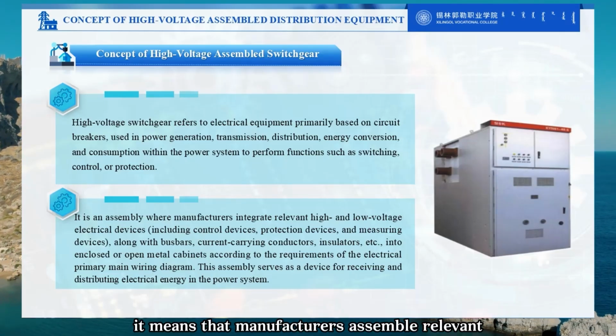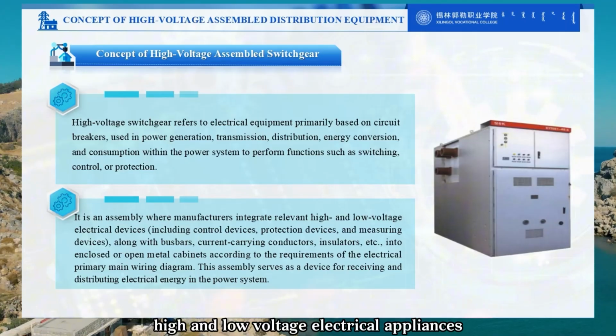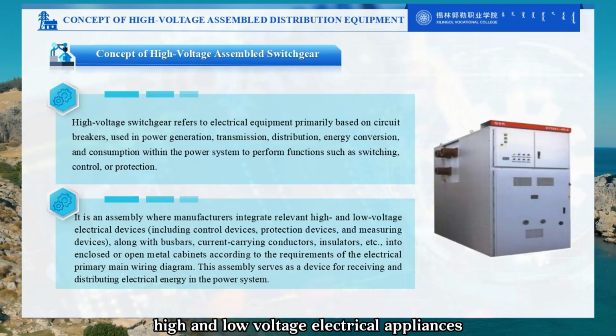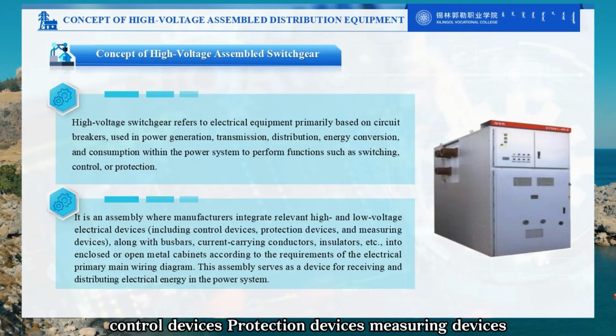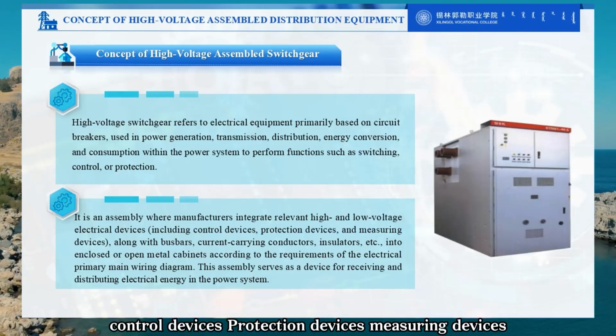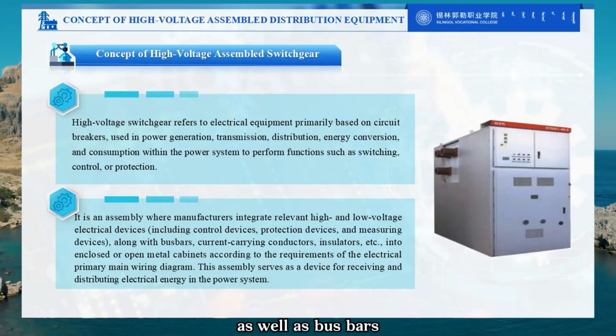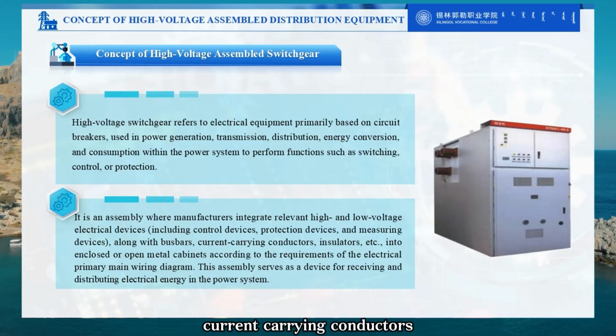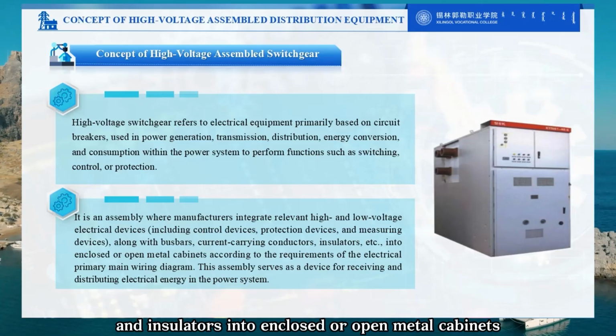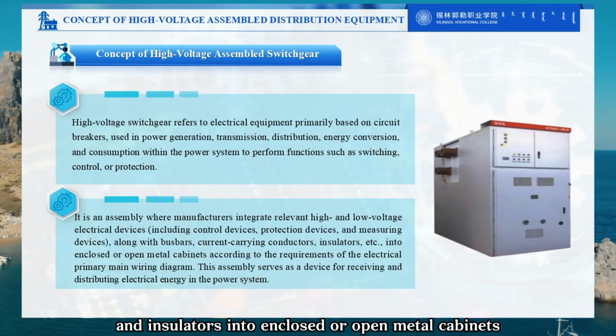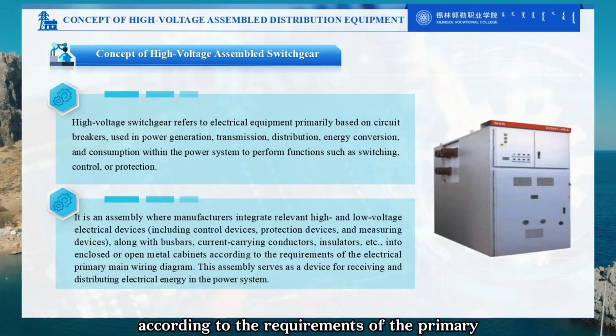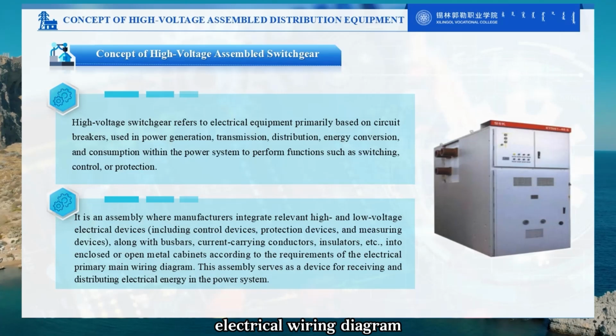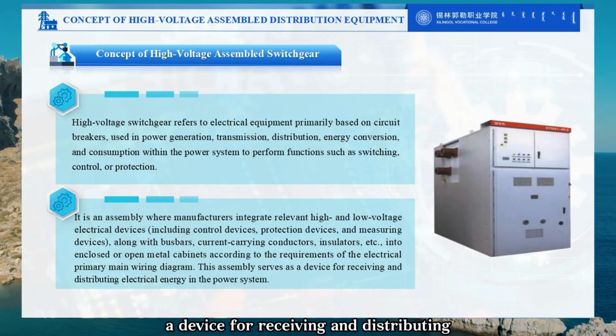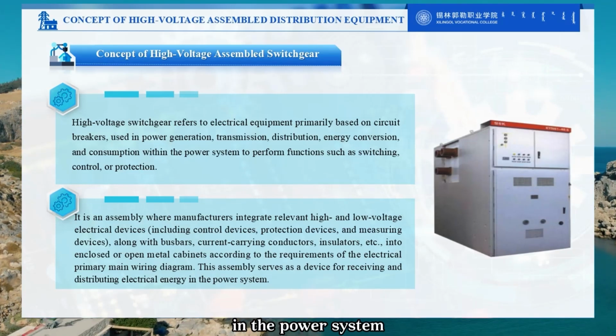It means that manufacturers assemble relevant high and low voltage electrical appliances, including control devices, protection devices, measuring devices, as well as busbars, current carrying conductors, and insulators into enclosed or open metal cabinets according to the requirements of the primary electrical wiring diagram. This serves as a device for receiving and distributing electrical energy in the power system.